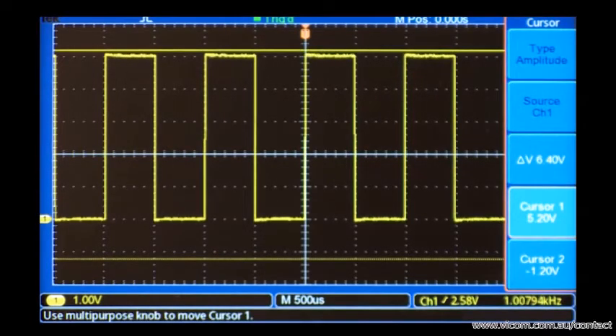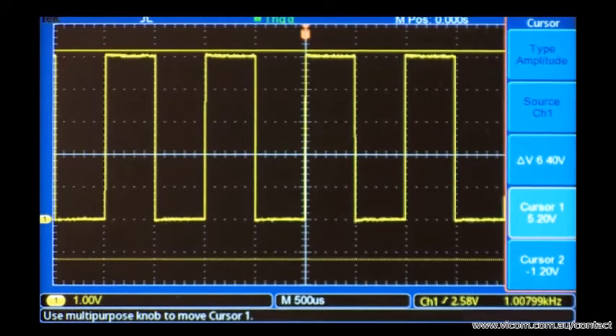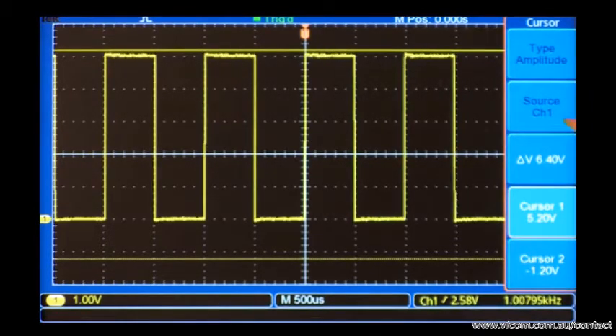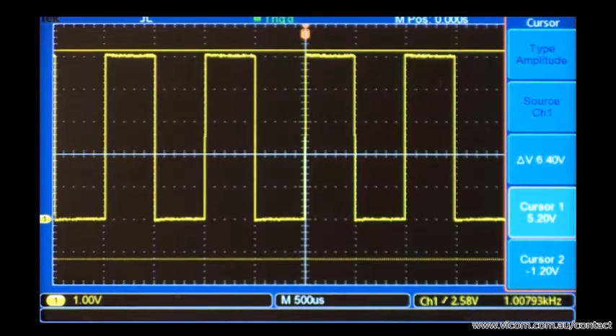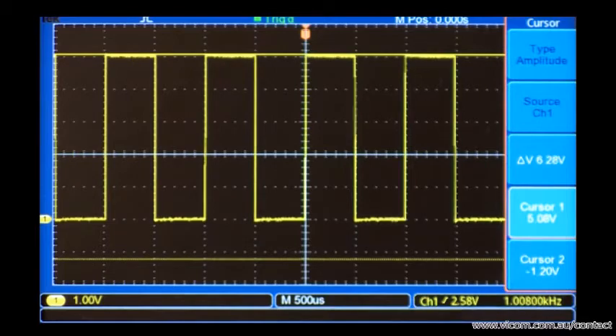This brings up two horizontal cursors. Since the signal is connected to channel 1, I need to make sure that it's the source for the cursor measurement. We'll use both cursors to make the peak-to-peak measurement. I'll set the first one to the highest point of the waveform.